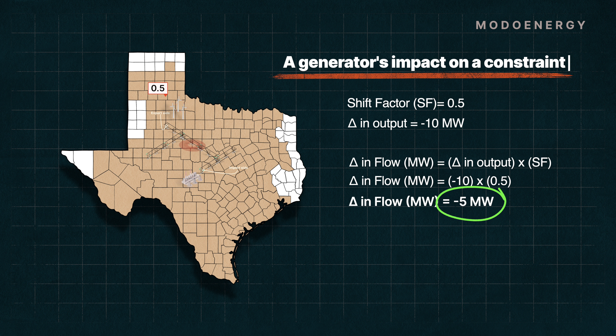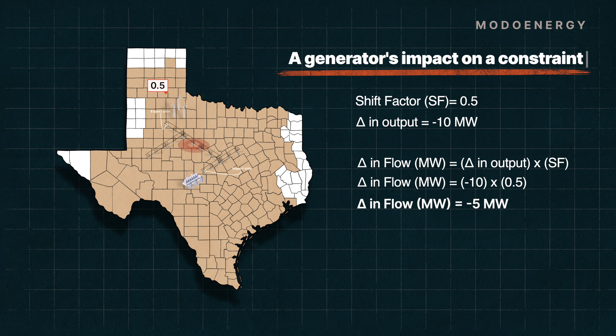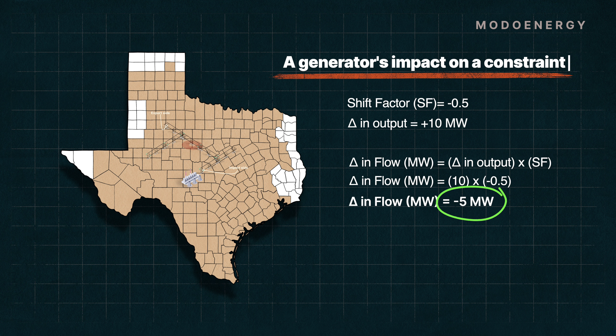Now imagine a generator on the import side of the constraint. This generator might have a shift factor of negative 0.5. If it increases its output by 10 MW, the flow across the constraint would decrease by 5 MW.